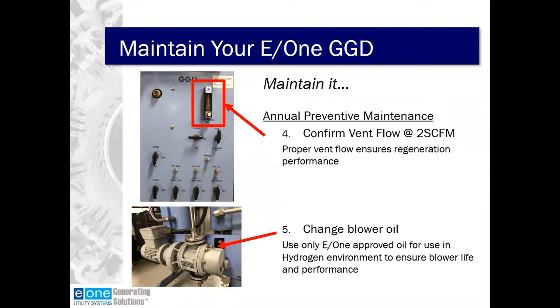One of the things we like to do and ensure during the annual preventive maintenance is to confirm that the vent flow is set properly, and that's at 2 standard cubic feet per minute. The flow meter located on the front panel indicates how much hydrogen gas is flowing when the regeneration process is occurring.